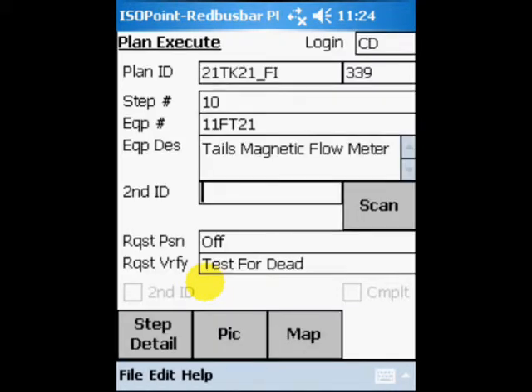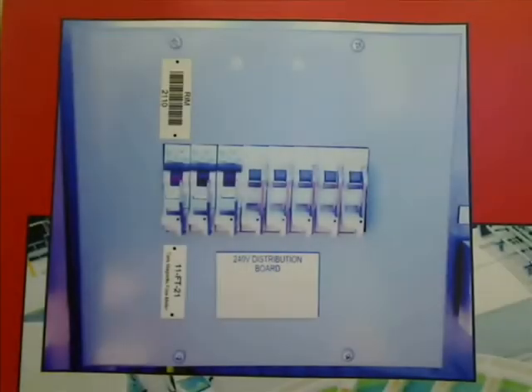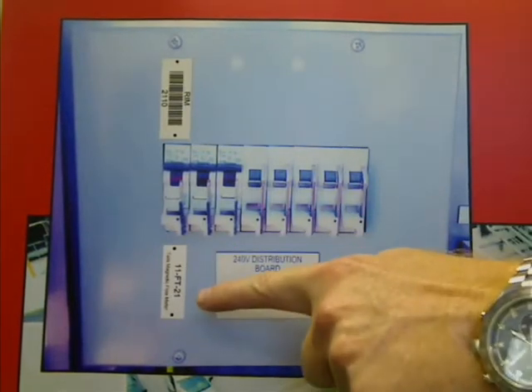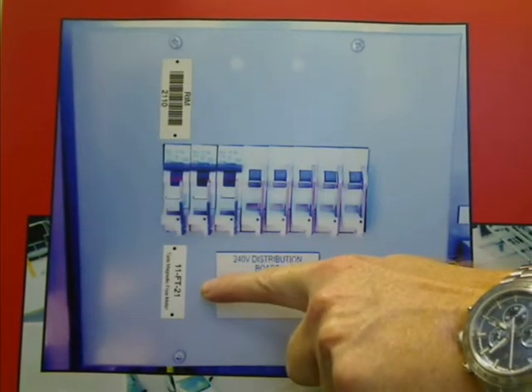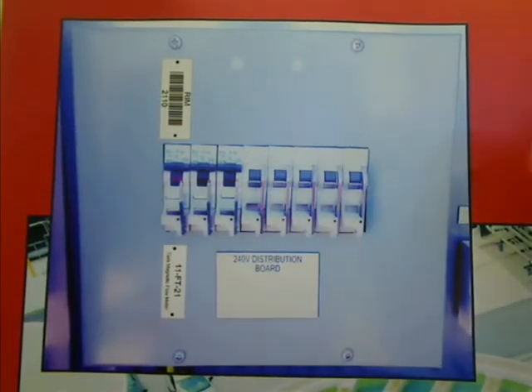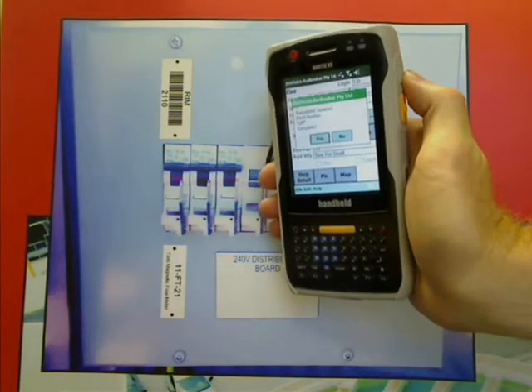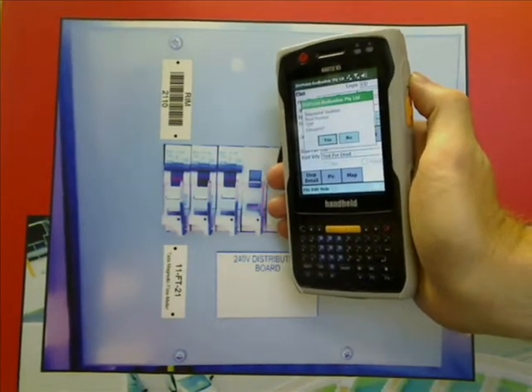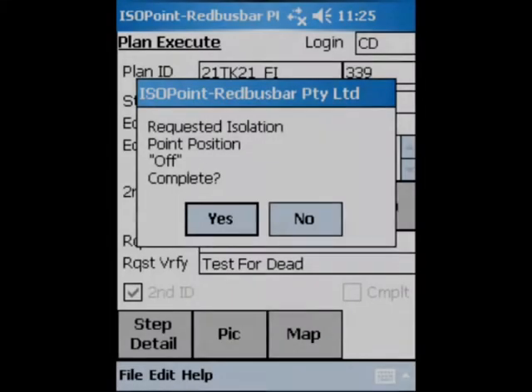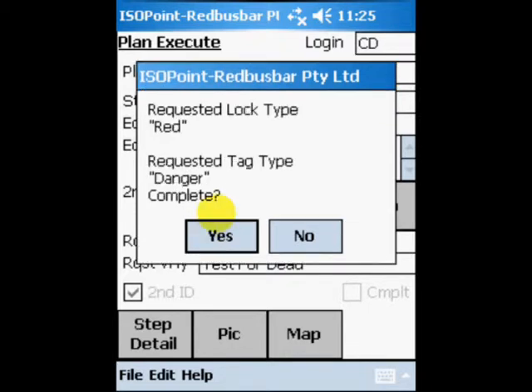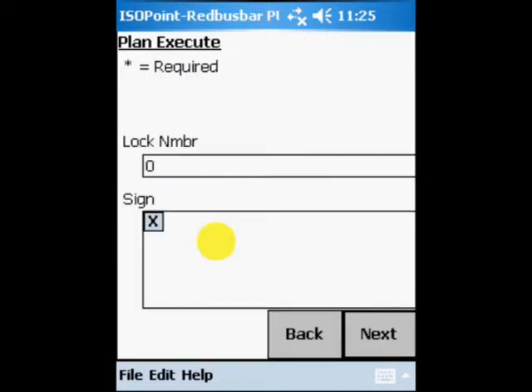Selecting Execute Plan commences the isolation procedure. The first step is to isolate 11FT21. This text label identifies this circuit breaker as 11FT21. Scanning the barcode confirms the identity of this circuit breaker as being 11FT21, as the PDA advances to a prompt requiring confirmation that the switch has been turned off. Various prompts require the isolation officer to confirm the target position of the isolation point.